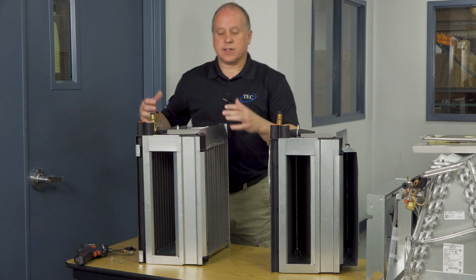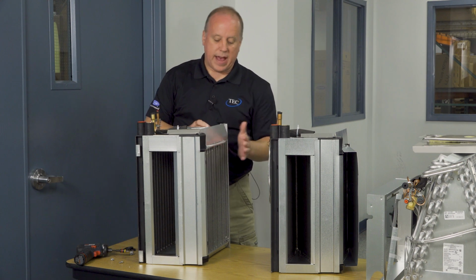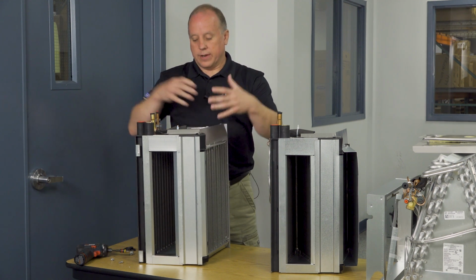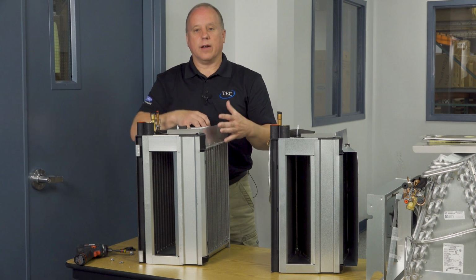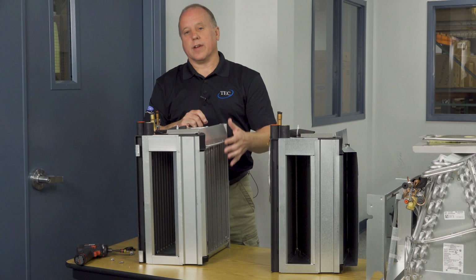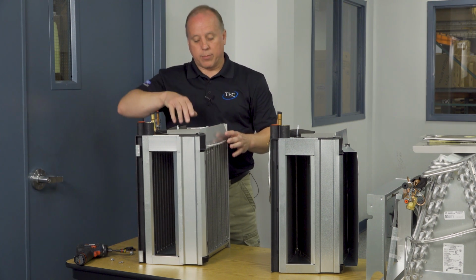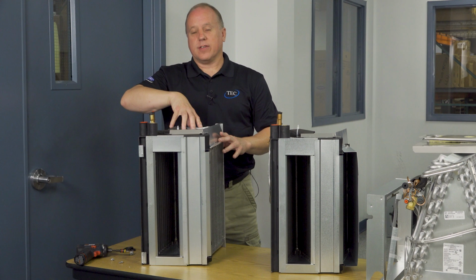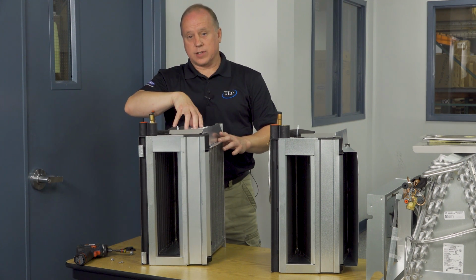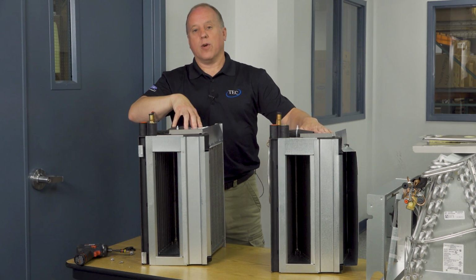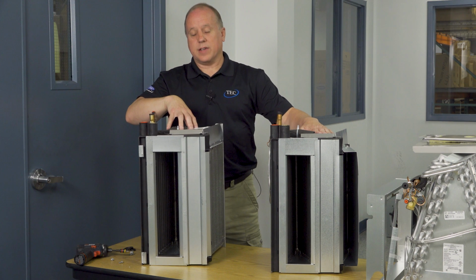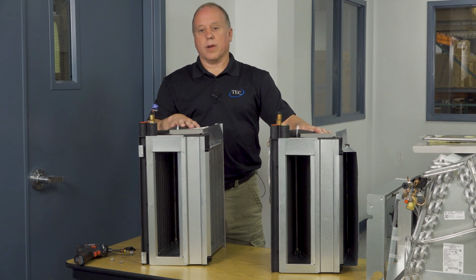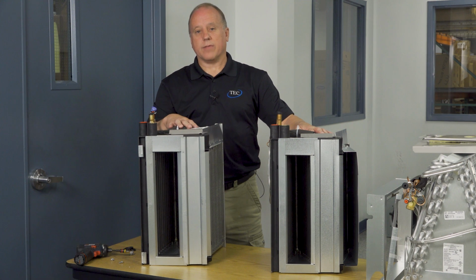If we pull this out of the case, slide this into a plenum, if we don't have this baffle on this side of the coil, and air gets past here, we're gonna obviously run into problems with the refrigerant traveling through this coil, no airflow through the coil. We're gonna see temperatures dropping, freezing up, low pressures. Obviously, our AC isn't gonna work properly. So, rule on this. We do not uncase the end coils and use them in uncased applications. Specifically, uncased end coils for uncased applications, cased end coils for cased applications. It's not the same as an A coil, so we ought to make sure we keep that straight so we don't run into problems after the install, and now we have to go back and correct that after the fact.